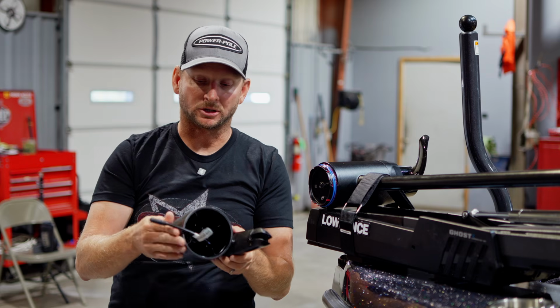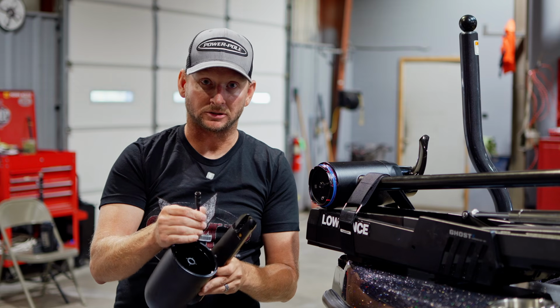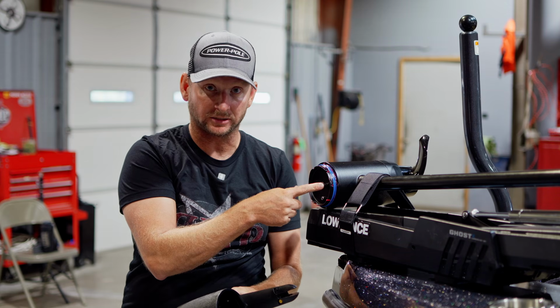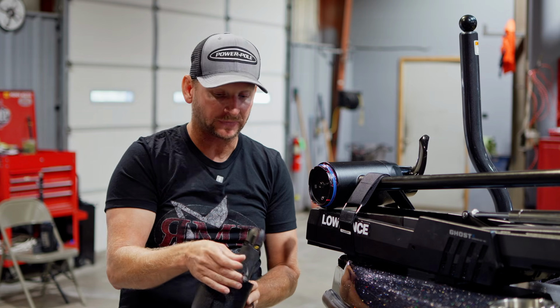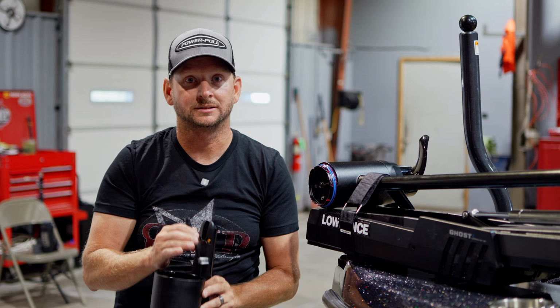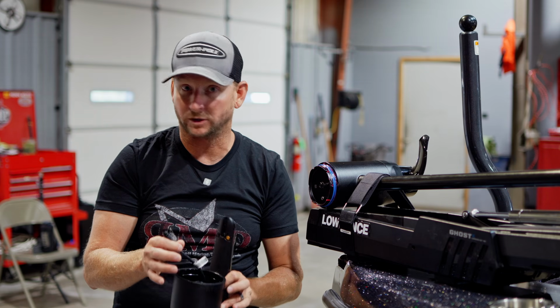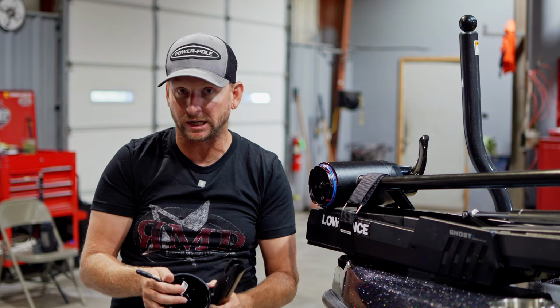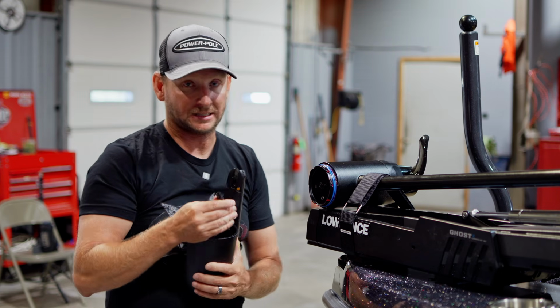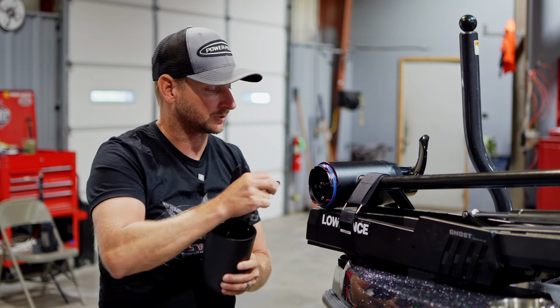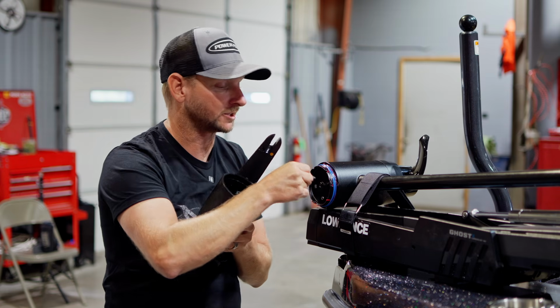Next, we have our nose cone here, and here's the end of the transducer cable. That's going to plug directly into where we took off that little black cap. Do not force this—it will go on one way and one way only. Break pins, bend pins, and it's a challenge to get them straight and working again. These are pretty expensive, so don't break it.